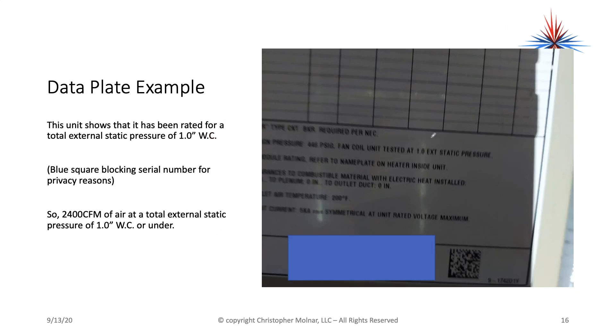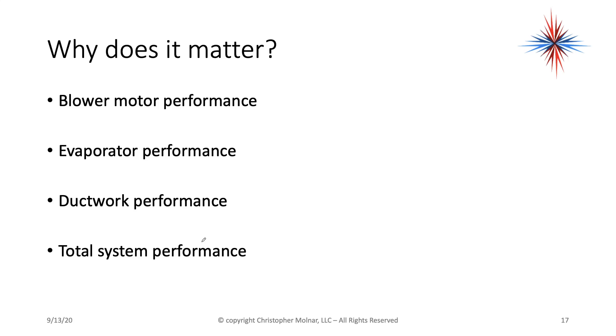There's one more thing to find on the data plate: what the unit was tested at for external static pressure. The unit is rated for 1.0 inches water column total external static pressure. So 2,400 CFM of air at a total external static pressure of 1.0 inches water column or under. This all goes into blower motor performance, evaporator performance, ductwork performance, and total system performance.